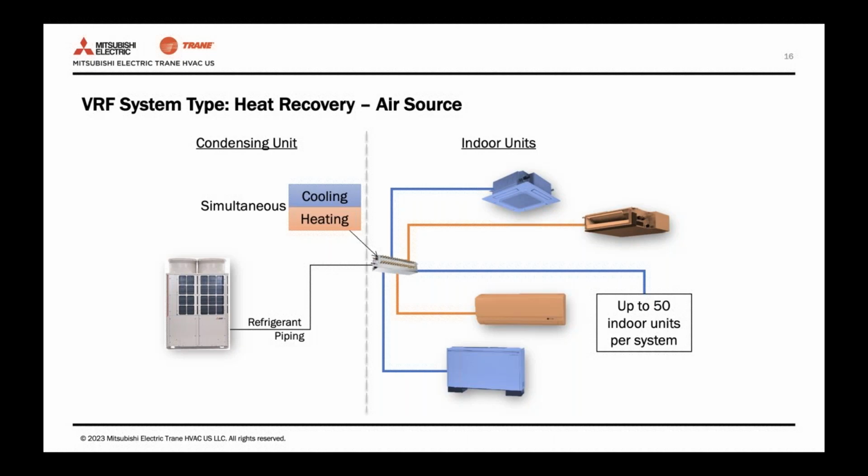These systems are great for resident rooms where one VRF system can service an entire wing of the building. Think of the reduction in electrical wiring and breaker sizes now, not to mention all the roof penetrations comparing this to one-to-one split systems. These heat recovery VRF systems save you even more energy by recapturing waste heat from rooms in cooling mode and reusing that waste heat through the refrigerant cycle to heat other rooms. And anyone operating a senior living community knows that seniors need and want heat, and many times have their rooms in heating mode, even in the summer when outside temperatures are warmer.